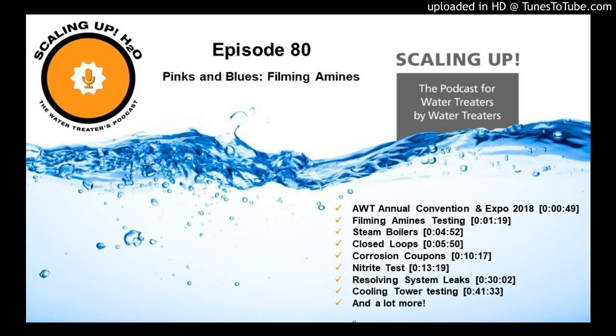So folks, if you ever run out of product, or you have a leak in your system and you think, oh, I'm just going to get to that next month, or the customer doesn't think it's important to tell you that they just lost a bunch of water in their closed loop system, look at this lid and compare 2 days before and 2 days after. I guess it was almost 3 days before and after. You will see that there is obvious orange rust on that lid. It does not take long for us to damage that nice protective coating that we have in the system. So it is imperative that we treat the system all the time.